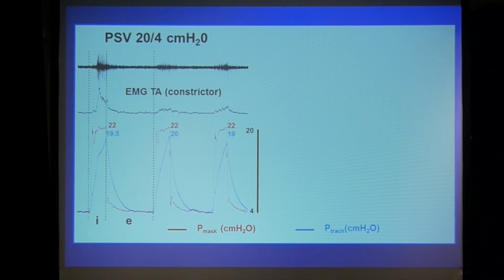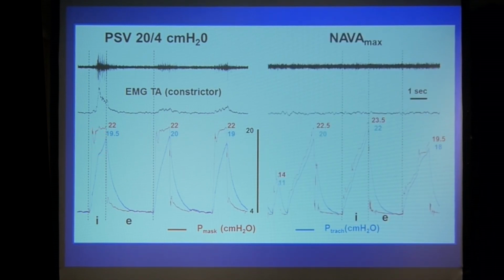This is to show you again the glottal constrictor during inspiration with the burst of activity. In red you have the mask pressure, and in blue you have the tracheal pressure. As you can see, there is a difference between the two. If you look now at NAVA for about the same peak inspiratory pressure, you can see that the tracheal pressure wave follows the mask pressure wave.